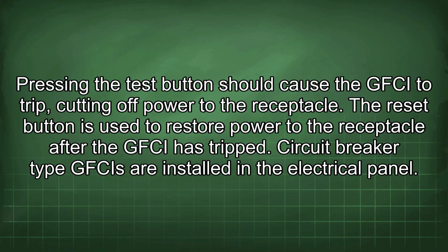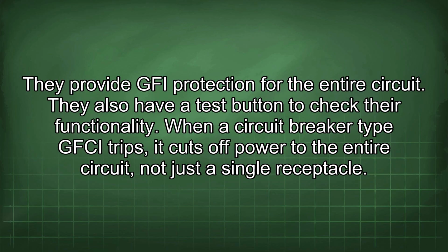Circuit breaker type GFCIs are installed in the electrical panel. They provide GFI protection for the entire circuit. They also have a test button to check their functionality. When a circuit breaker type GFCI trips, it cuts off power to the entire circuit, not just a single receptacle.